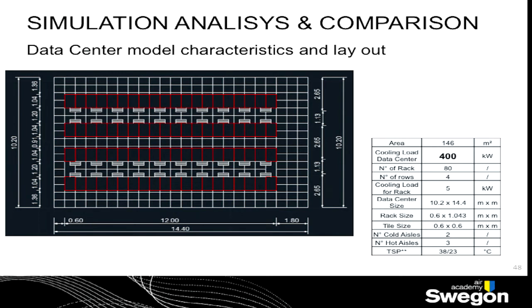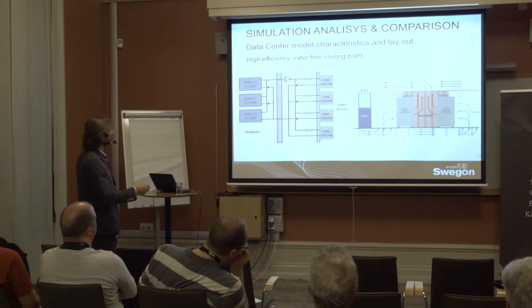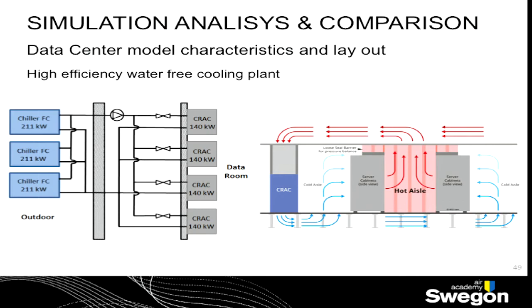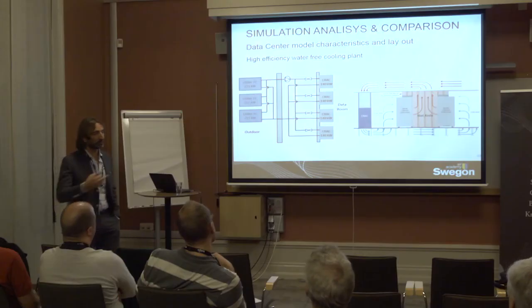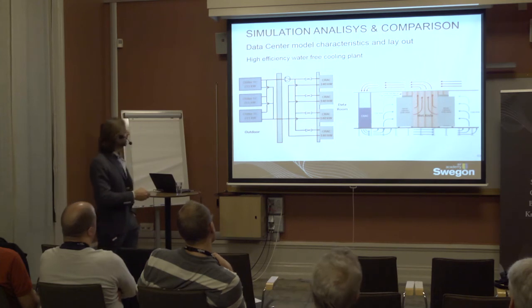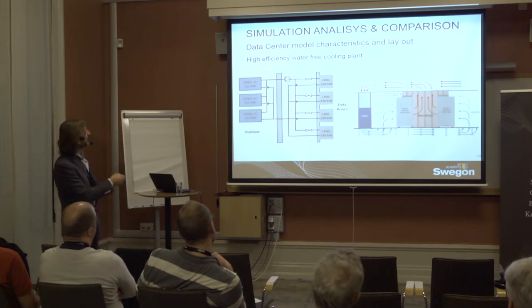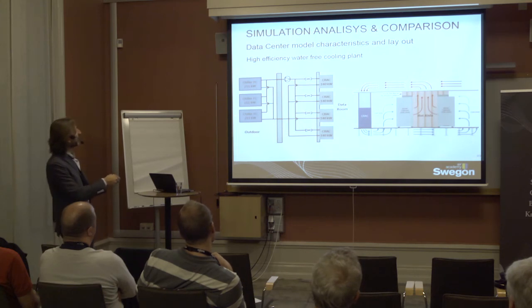The two systems that we considered are: a very efficient, probably the most efficient, free cooling system based on water technology that you can find on the current market, that uses CRAC units inside to move the air and to release the energy into the building, and that uses chillers equipped with free cooling to produce the cold water outside of the building. So the system is made like this one. We have got free cooling chillers outdoor, and we have got 4 CRAC units inside.